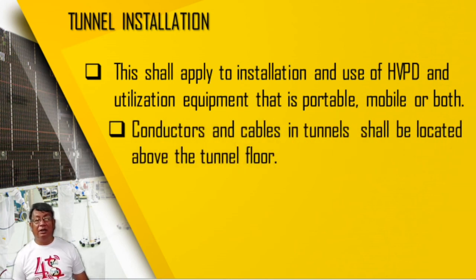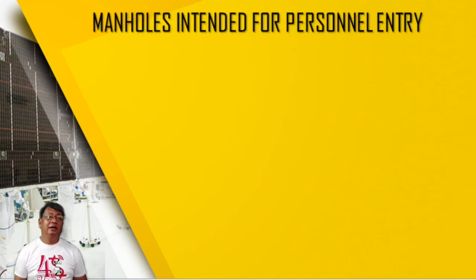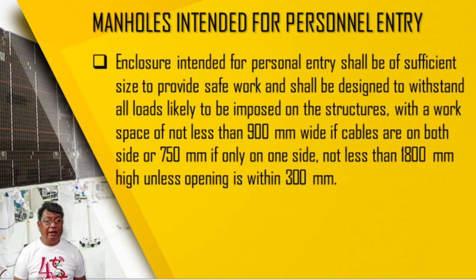Conductors and cables in tunnels shall be located above the tunnel floor. So in tunnel installations, the conductor should not be placed at the floor, but should be placed above the floor, or overhead in the tunnel. Manholes intended for personnel entry: enclosures intended for personnel entry shall be of sufficient size to provide safe work and shall be designed to withstand all loads likely to be imposed on the structure, with a workspace of not less than 900 mm wide if cables are on both sides, or 750 mm if only on one side, and not less than 1800 millimeter high.